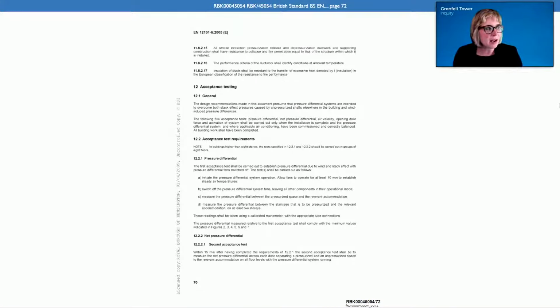So at the bottom of the page, we've got the airflow criterion between staircase and lobby. And it says the air supply should be sufficient to maintain that 2 meters per second through the open door between the staircase and the lobby at the fire affected story, with the air release path on the floor still open, and all of the following doors are open. So you've got all the doors between the lobby and the fire affected fire compartment open, the stair and the lobby on the story below the fire story open, the firefighting lift shaft on the lobby on the story below the fire story open, and it goes on.